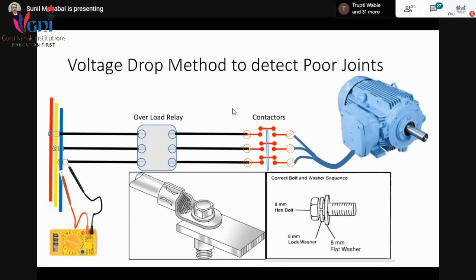So over a period, the aluminum will react with the copper. There will be a chemical reaction between the aluminum and copper. And even though you have tightened it, suppose say 2 months ago or 3 months ago, the joint can loosen on its own because of the chemical reaction. That was the new learning for me, that this can also happen. That the lug, if it is not of the same metal, then the chemical reaction, corrosion, can result in loose contact.